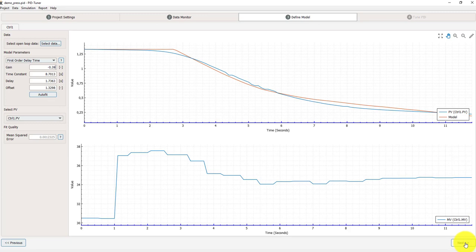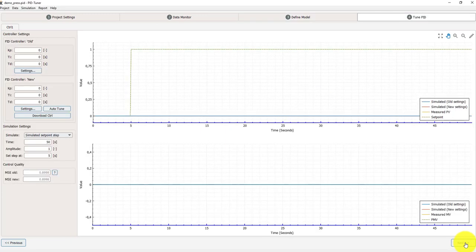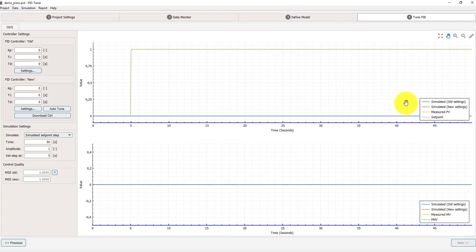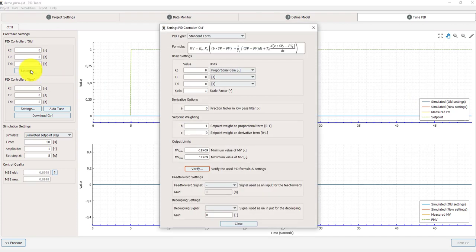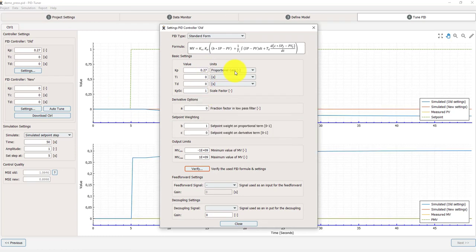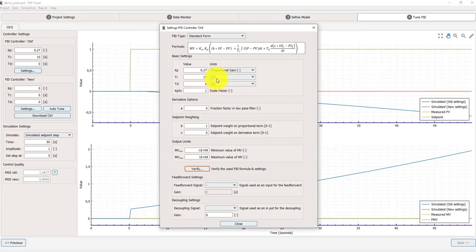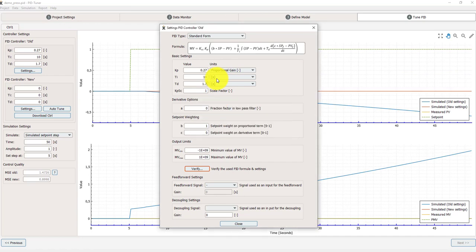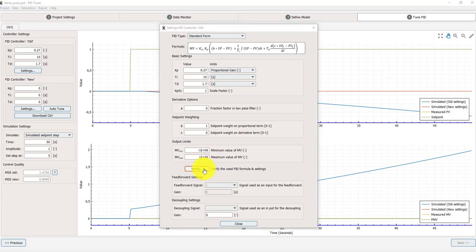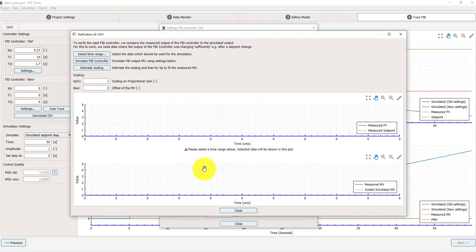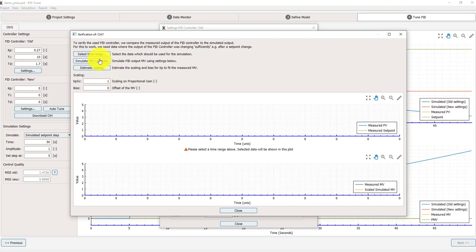You move on to the next part of the tuning. And now before you retune the PID you should first check if the old settings are alright. So what I'll do is I'll put in here the old settings. If you didn't have old settings you obviously cannot. You can skip this step. So I'm going to type in the old settings. And then I'm going to check if the old PID settings were right. If they match data.